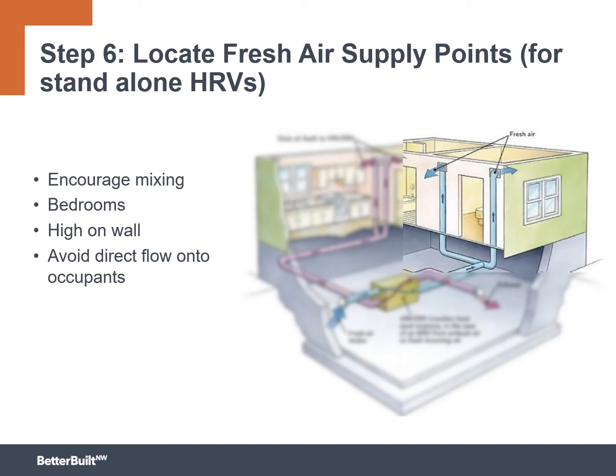So one option that we've heard people thinking about is putting these into closets. And that can work, but if you put it into the closet, a couple of things need to happen. You don't want to put it directly over the shelves. You know that Aunt Sylvia is going to cram a bunch of hat boxes up there and is likely going to disturb that airflow. Also, if it's in a closet, it's ideal to have it right over the door where some of those openings are. And speaking of the door, the closet door will need to either be undercut or probably louvered to get the best results. You don't want to just ventilate the closet. If you have a tight closing closet door, it doesn't really help you that much.